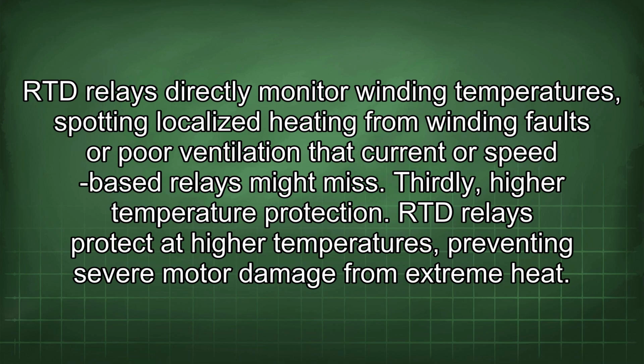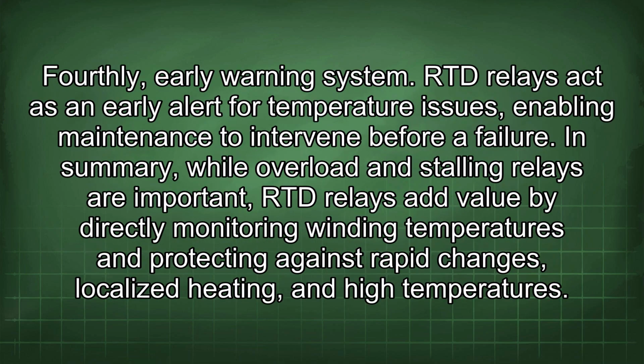Thirdly, higher temperature protection. RTD relays protect at higher temperatures, preventing severe motor damage from extreme heat. Fourthly, early warning system. RTD relays act as an early alert for temperature issues, enabling maintenance to intervene before a failure. In summary, while overload and stalling relays are important, RTD relays add value by directly monitoring winding temperatures and protecting against rapid changes, localized heating, and high temperatures.